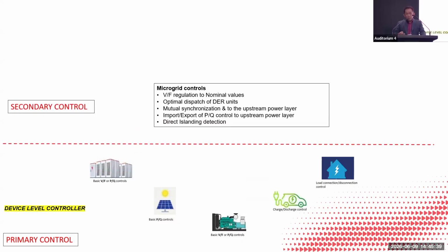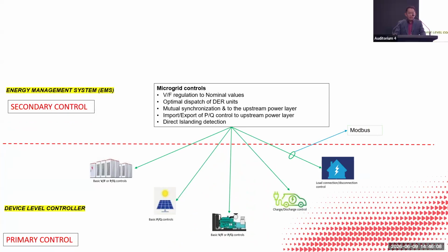On top of it, we have a secondary control level, which is where the EMS controller sits. This EMS controller takes care of the import-export limit, the V-F-P-Q, and also the islanding detection. All these devices communicate to the EMS control via Modbus. We call this a secondary control device.